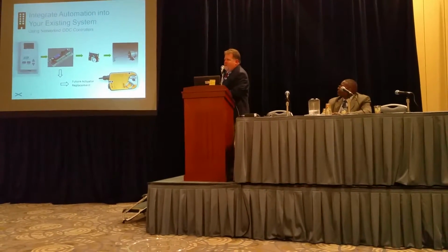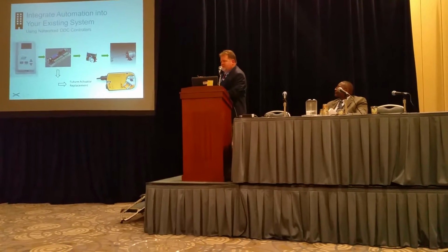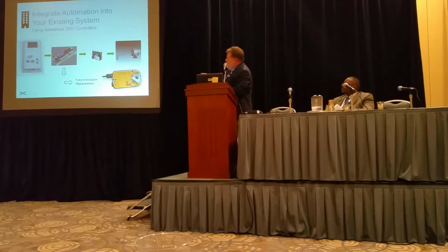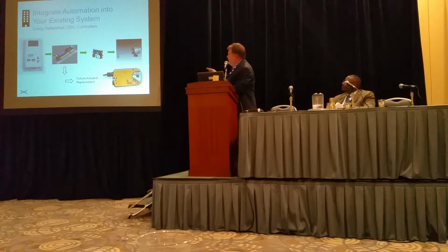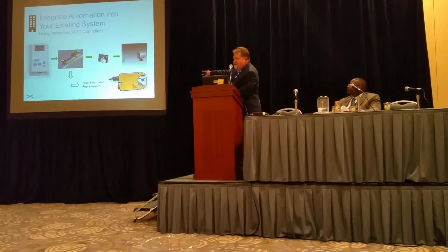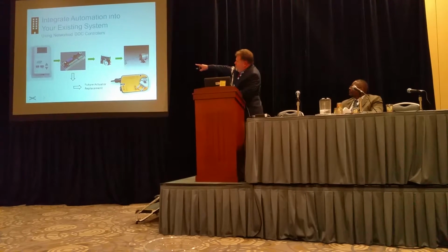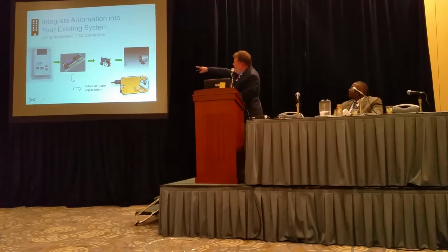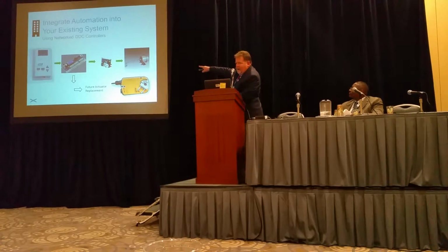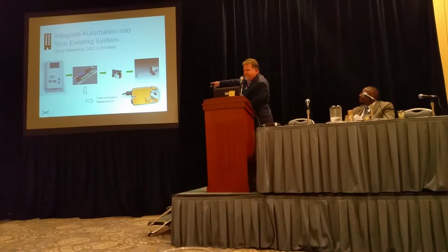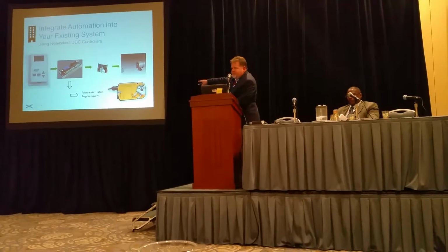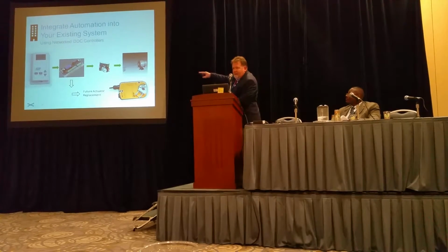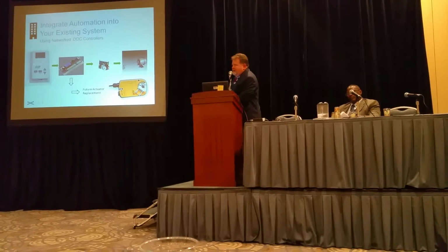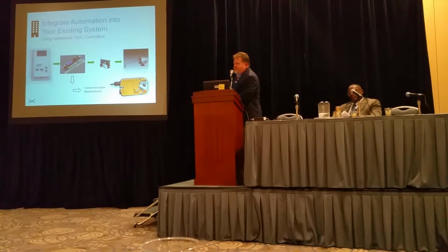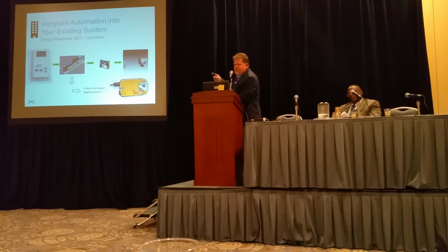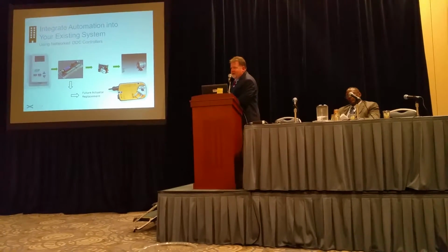Now if you say, well Mike, that's a waste. I have old pneumatics. Why do I want to convert and put digital to control old pneumatics? Well, the nice part about it is if the valve breaks, if there's a problem with the pneumatic damper actuator, then go ahead and put in a digital one at the bottom. So what we do is we go from the thermostat to the control board, and now instead of taking the two wires going to the pneumatic transducer to send air to the damper, just extend those two wires to the new damper. And a slight programming change would take 2-3 minutes. Now all of a sudden you're controlling that damper rather than controlling the transducer to send air. So in essence, you can add automation to an existing pneumatic system. In the next 20 years, that pneumatic system will be converted over to digital at little to no cost for the integration.